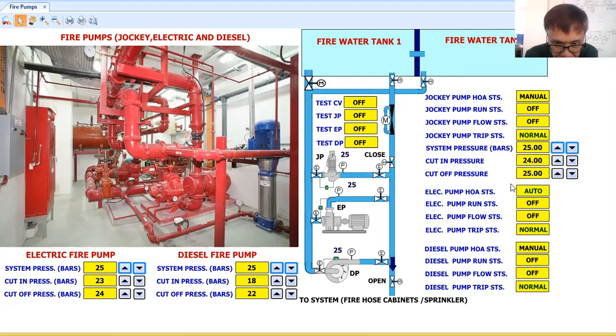Because if you are not going to install a jockey pump, there is a danger that the electric pump will run. For a small leak, we don't want the electric pump or the diesel pump to run because it might damage the system, because there is no actual bursting of the sprinkler heads, okay? Now, let me do some animation again. Okay, now I have a small leak. Then my pressure keeps on dropping. Now the cut-in pressure of my electric pump is 23. So as you know now, 23 bars is more than enough to start my electric pump.